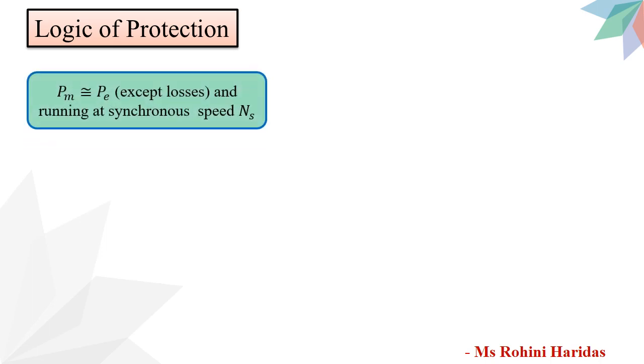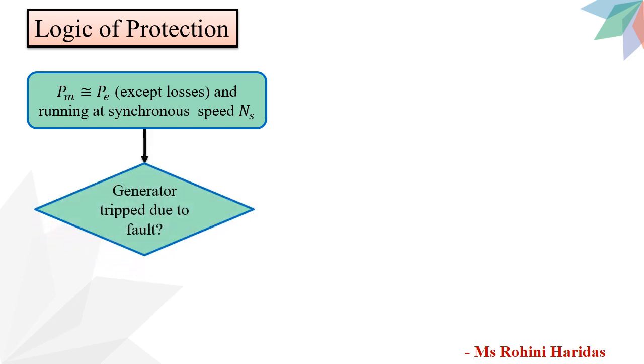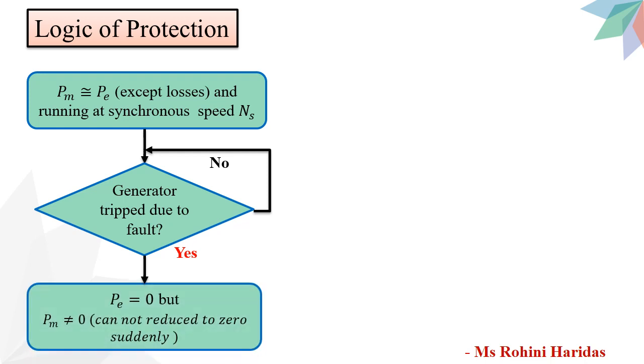Now let us see the logic behind the protection against overspeeding. Let us consider that the alternator is supplying its rated electrical power PE to the grid, and its mechanical input PM is nearly equal to PE, and the machine is running at constant synchronous speed. Now consider that due to some fault, the generator is tripped and disconnected from the grid. So PE, that is electrical power, will be equal to 0.